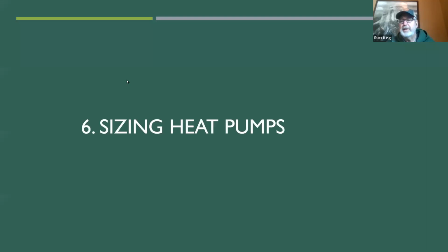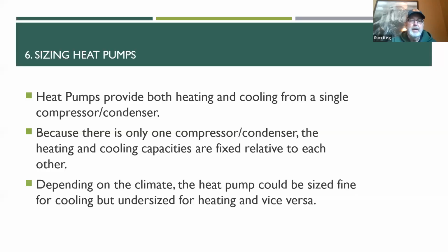All right, how do you size heat pumps? This is a very complicated issue. And this is where people get into a lot of trouble. Heat pumps need to be sized correctly, okay? Heat pumps provide both heating and cooling from a single box, the compressor condenser box. That one unit provides heating and cooling. So you don't get a lot of choices between mixing and matching your capacity. Like if you have a separate furnace, you can get different size furnaces and match that with a different size air conditioner. Well, a heat pump does both. So the relationship between the heating and cooling capacity is fixed.